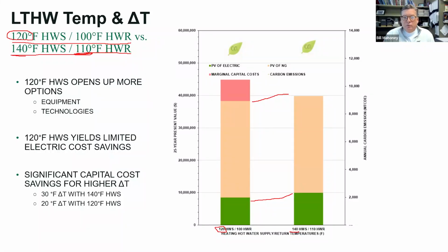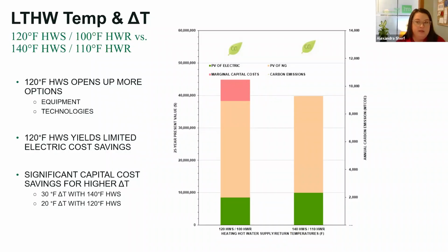The big driver here into which way to go in the life cycle cost analysis was the pink up here, and that was the marginal capital cost, not the total capital cost, which were a lot more, but just in marginal capital cost. How big? I think the pipe sizes went from 24 to 18 inches for the heating water supply, and we ran a lot of piping in our analysis. And that was worth, you can see here, $5 or so million, and that's the driver. So you're saving maybe $1 million here and there in the energy cost, but that capital cost was the driver. Great. And so let's talk a little bit about the technology then that you recommended.